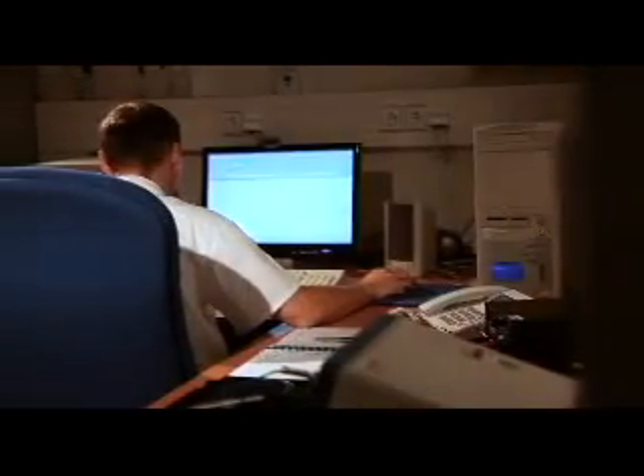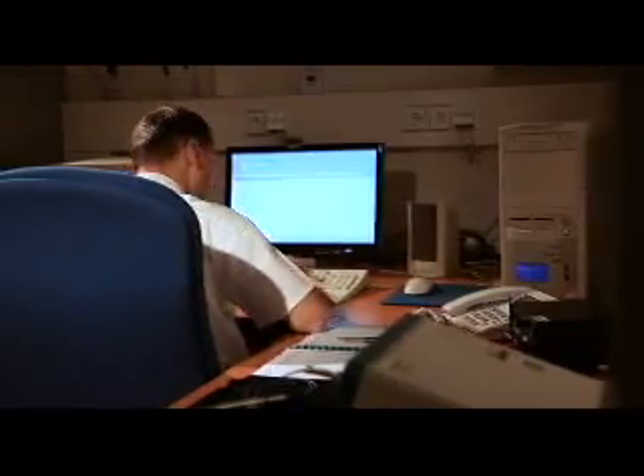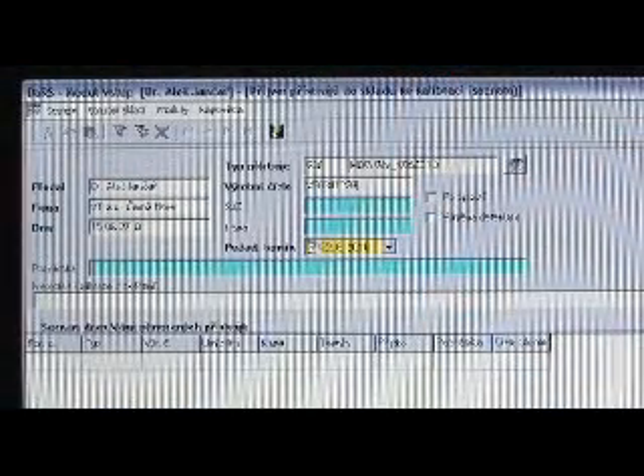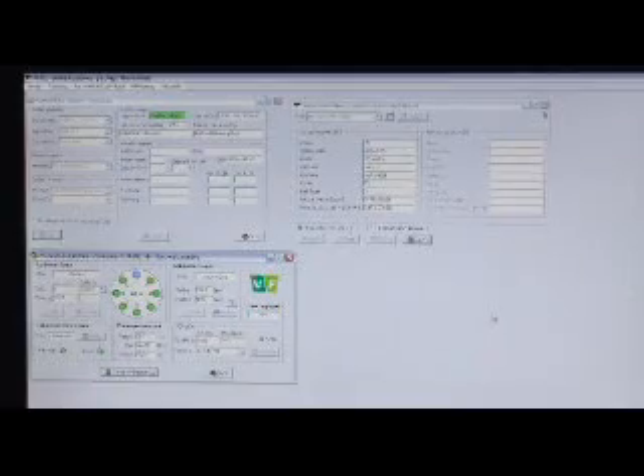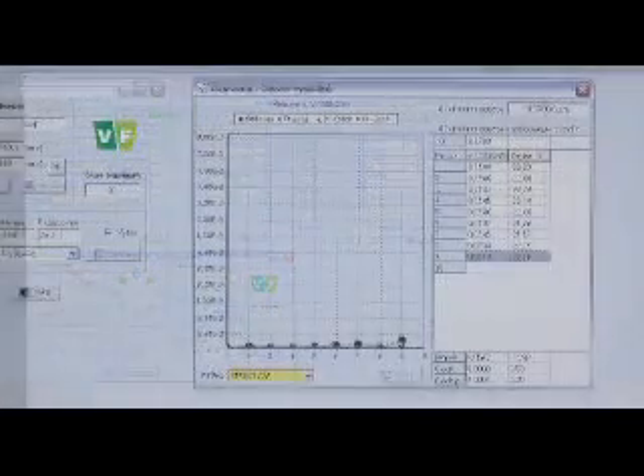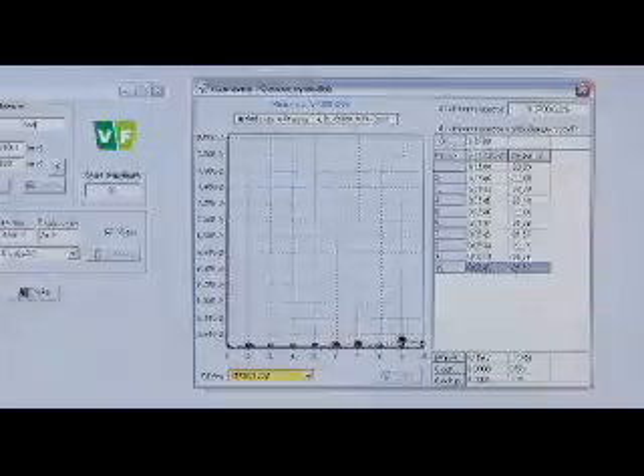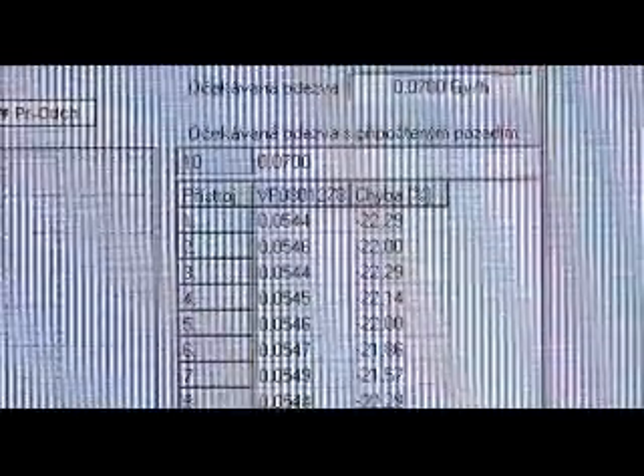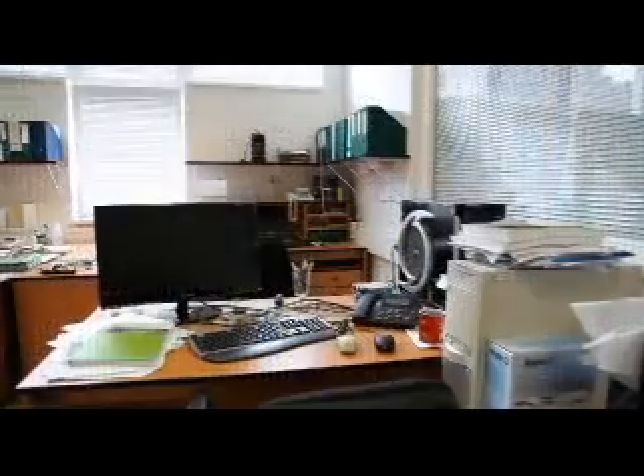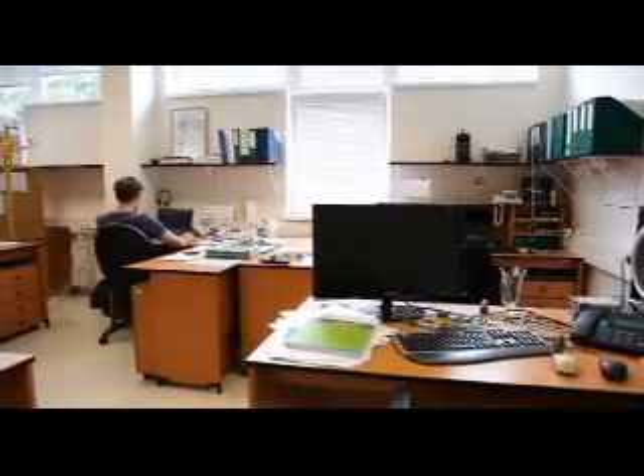The control and data management software of the calibration laboratory consists of three parts. A database register of all instruments received for calibration. Software for creation of automated calibration methodologies, printouts, and complete administration of the system. Application software enabling the remote control of laboratory facilities, a function which can be carried out by the operator or in a fully automated manner.